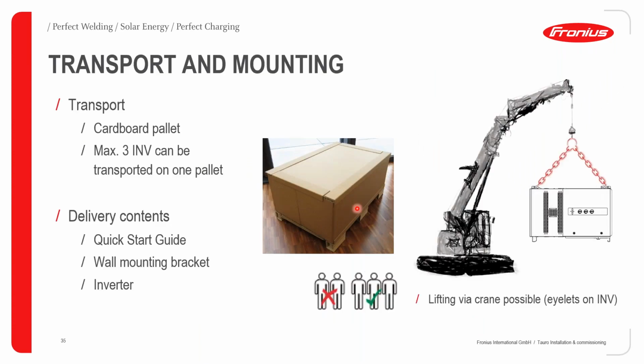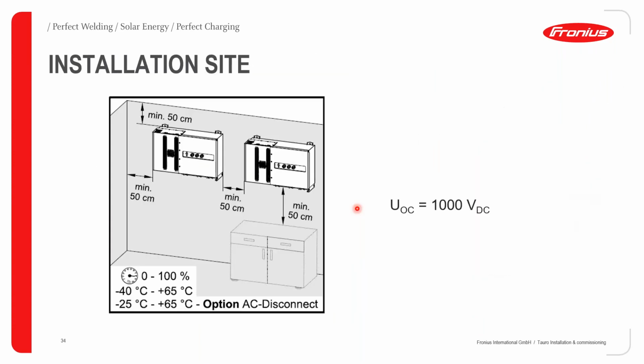Okay, moving on to the installation site. If you are going to install more than one Tauro inverter, or even if you're installing one Tauro inverter, please make sure that you do take adequate attention to these details. So what you do need is a minimum distance of 50 centimeters between the top of the Tauro and the ceiling. You also need a minimum distance of 50 centimeters between the side of the Tauro and the wall. You also need a distance of 50 centimeters between each Tauro inverter. The reason for this side distance is because hot air is going to be passed out from the sides of the inverter. So obviously it needs enough space to escape.